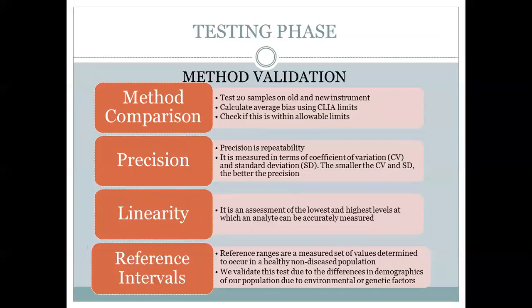And then we also test for precision. We want to make sure that our results are repeatable on this new instrument. It's not giving us a WBC count of 4 on the first result, and on the same specimen when we run again, it gives us a WBC count of 10. So we want to make sure that it's precise. And then we also validate for linearity to make sure that it runs the low levels of samples, analytes, as well as the high levels.